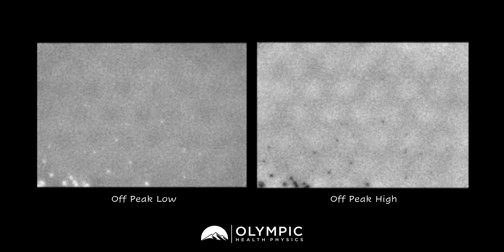Sodium iodide crystals are hygroscopic in nature, which means that they are going to tend to absorb moisture from the atmosphere. The crystals themselves are hermetically sealed from the atmosphere to not allow air to get in. But if that seal becomes compromised or degrades in any way, then atmospheric air can enter into the crystal and create hydration.